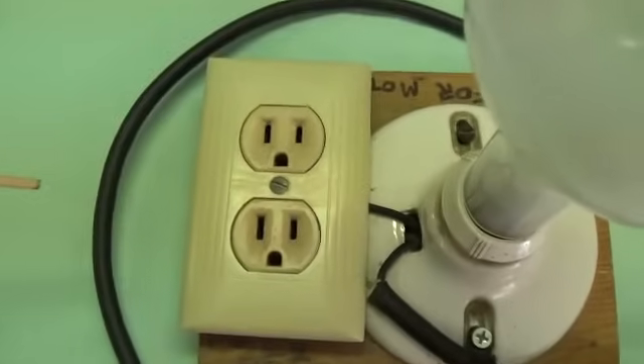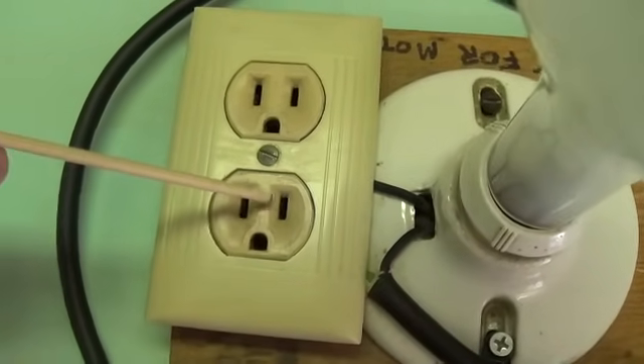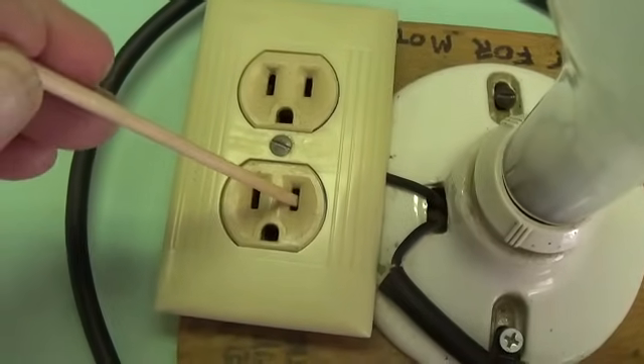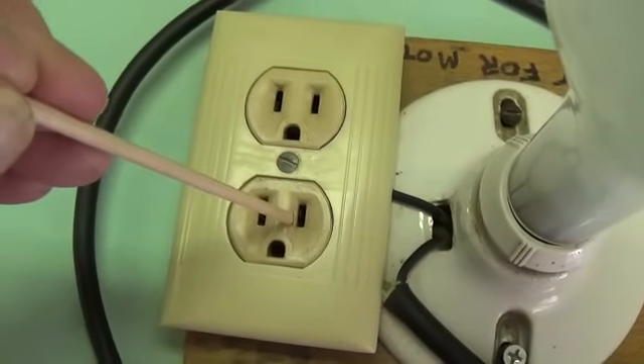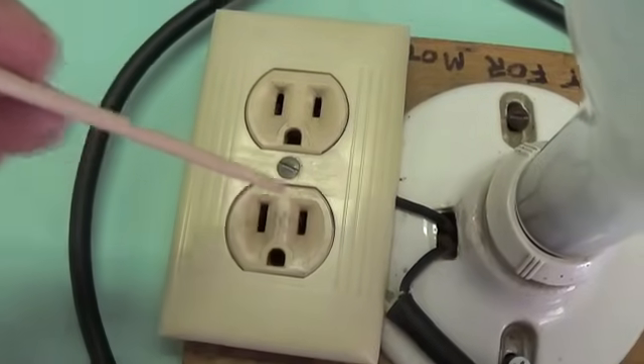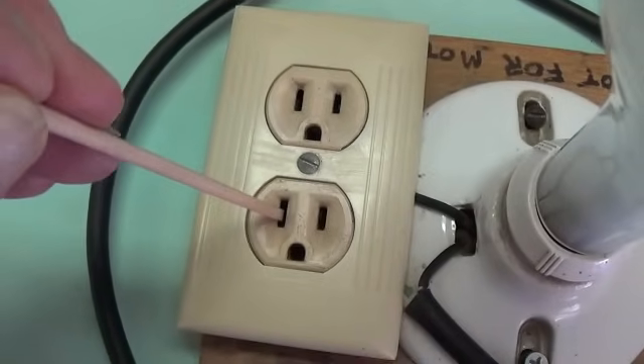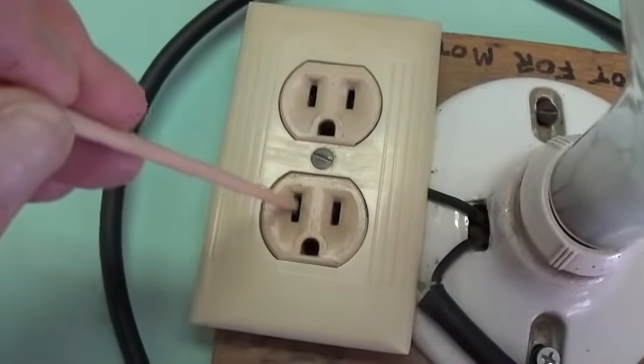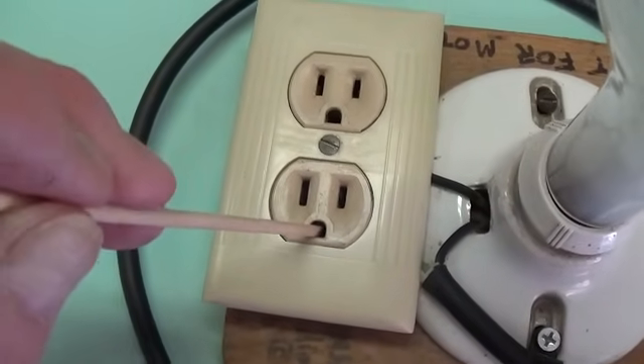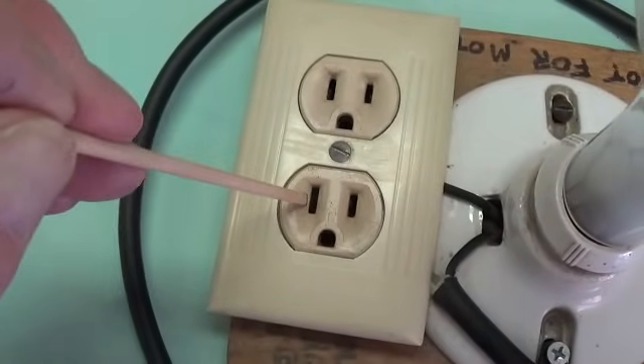I think a lot of people fail to understand that outlets are polarized for a reason. The narrower prong connects to a black wire. This is the hot connection. This is where the 110 volts resides. The wide plug hole is for a white wire, which is what we would call a common wire. And this one, I guess most people realize, is for the green wire or the ground. So, wide is white.